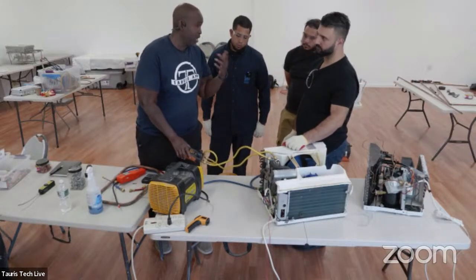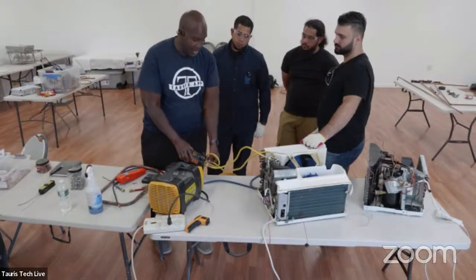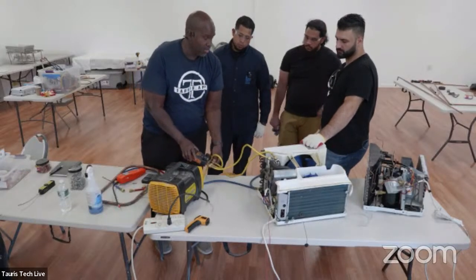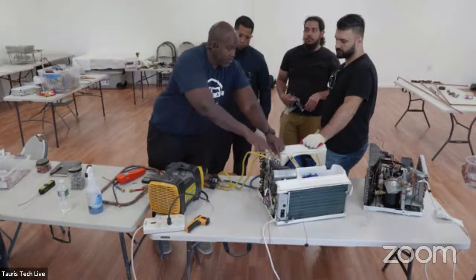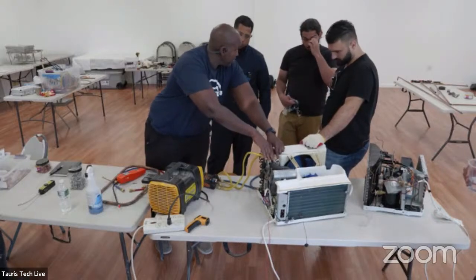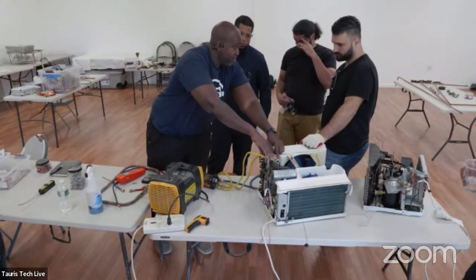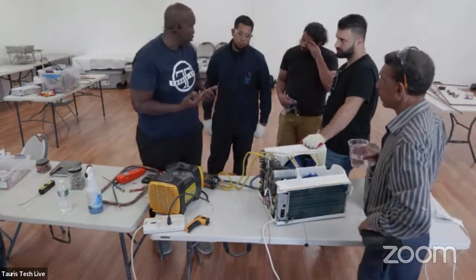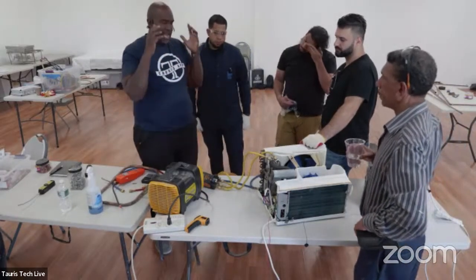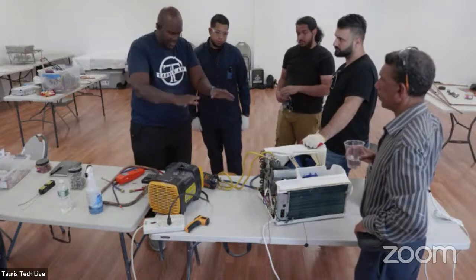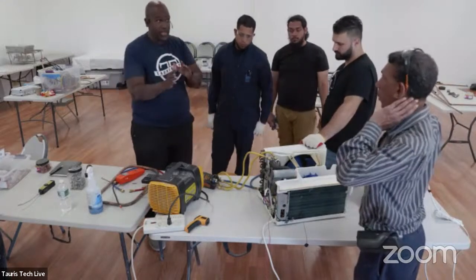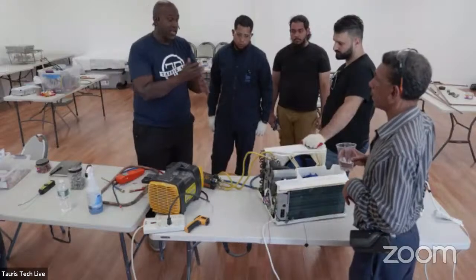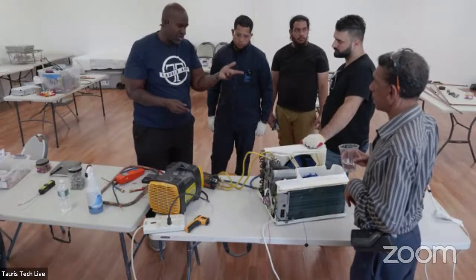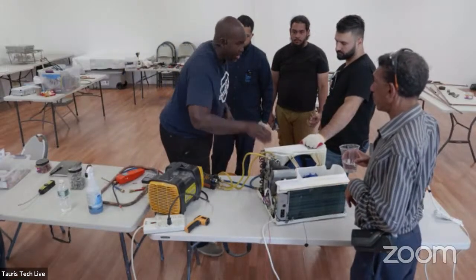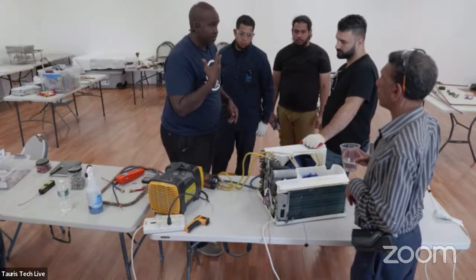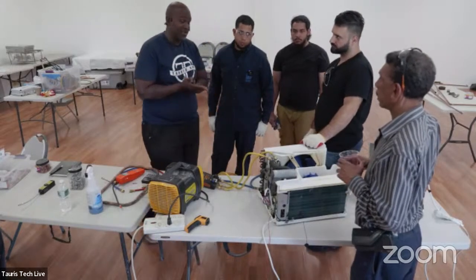But if I did, then I would want to make sure that I front seat. So if this isn't a vacuum, or if it has refrigerant, and I front seat, then I can take my hose off. You always have to understand this flow of refrigerant - where is it going, where is it coming from, is it safe? Because if it's refrigerant, let's say I'm charging refrigerant and I disconnect, boom, refrigerant on my face. And 410A, if it's under pressure, it's coming fast.